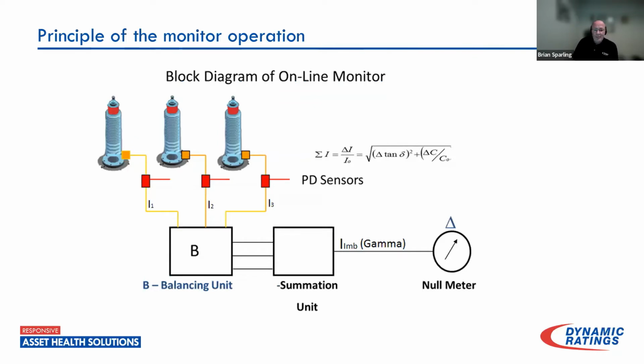So the principle of the operation looks like this. We have 3 bushings, each with their own tap sensor. The sensor signals come down into the monitor, into what we call a balancing unit, because each bushing, when it's energized, is going to have a different amount of leakage current coming out of it. We do a balancing and summation of the vector sum of the currents into the summation unit, and there's the equation that you see above it. And from there, we can arrive at a null point inside the monitor. And it's from that null point that we monitor both the increasing potential for increasing leakage current and/or phase angle of the measurement of each bushing in sequence.